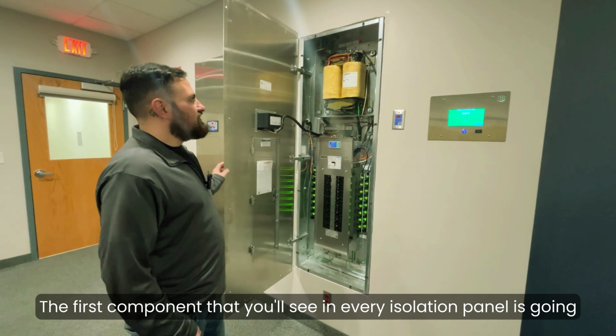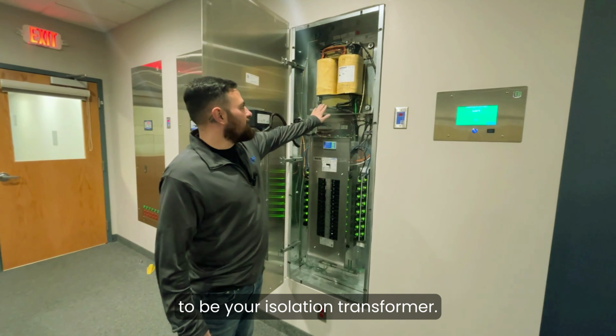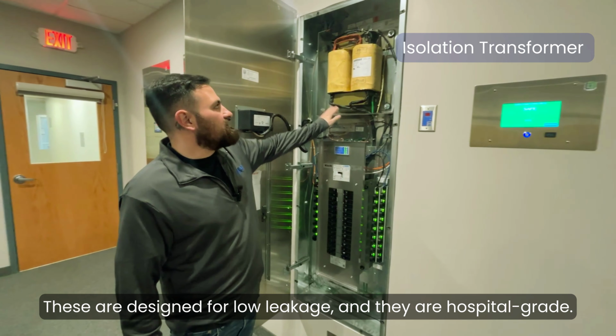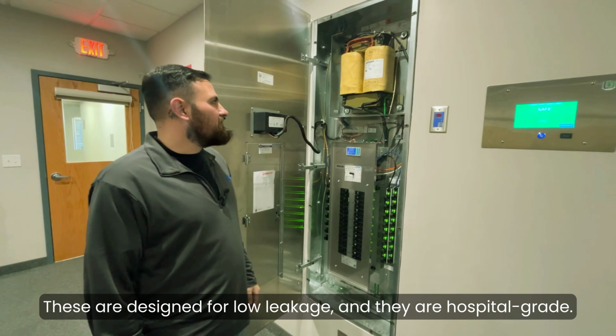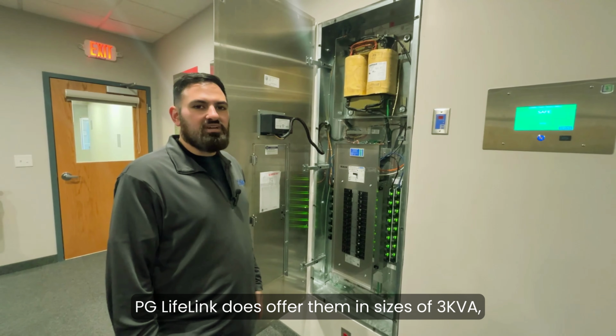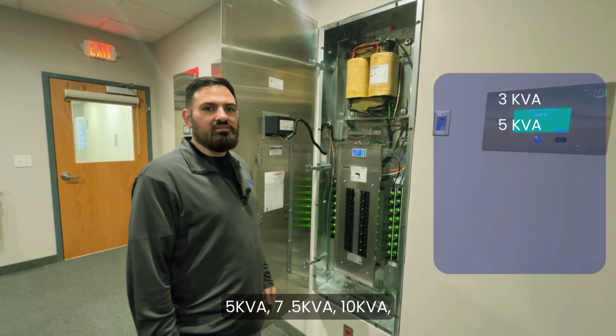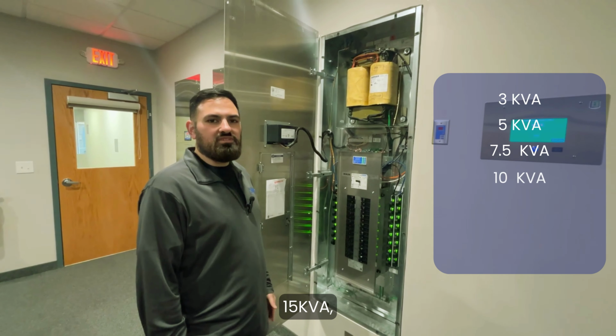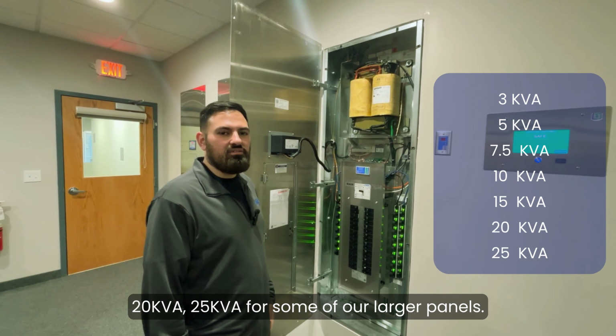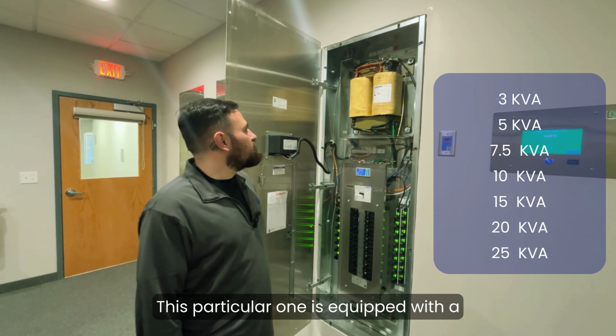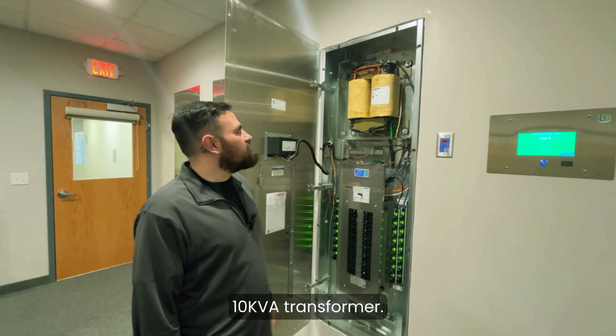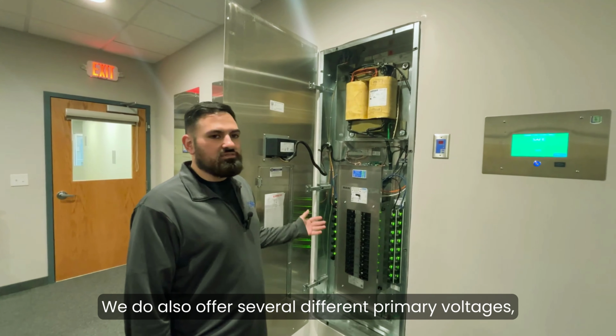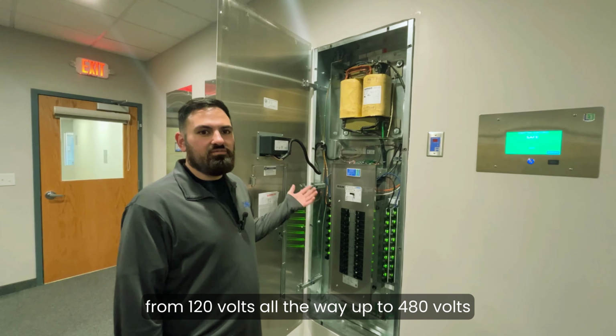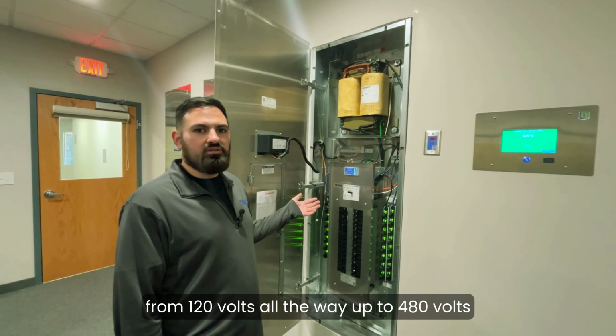The first component you'll see in every isolation panel is the isolation transformer. These are designed for low leakage and are hospital grade. PG Lifelink offers them in sizes of 3 kVA, 5 kVA, 7.5, 10, 15, 20, and 25 kVA for some of our larger panels. This particular one is equipped with a 10 kVA transformer.